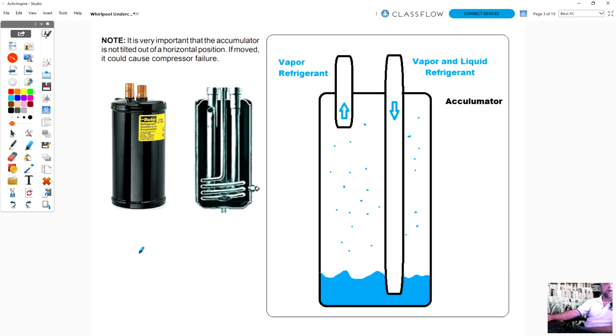I have here a drawing of an accumulator, and when we have a system running normally, it pumps high pressure refrigerant into the condenser. It converts that vapor into liquid refrigerant, and that goes through a capillary tube to the evaporator, and the heat of the evaporator is supposed to turn that liquid back to a vapor. That's the normal cycle. But if you're bypassing the condenser and you're going over the evaporator to release the heat, it is possible some of the refrigerant in liquid form can get back to your compressor and damage your compressor.